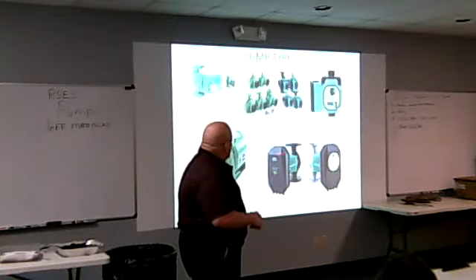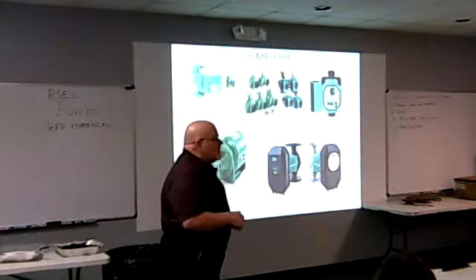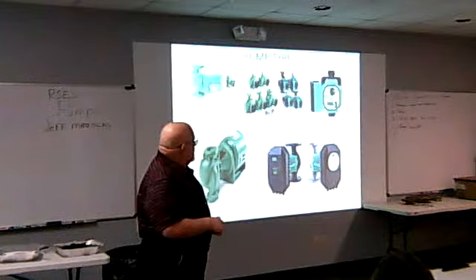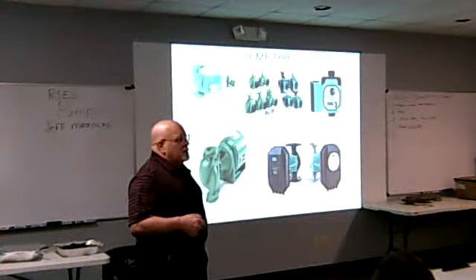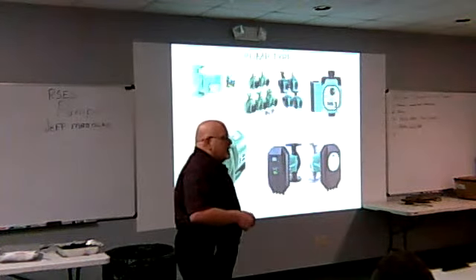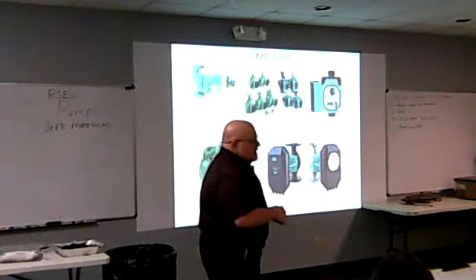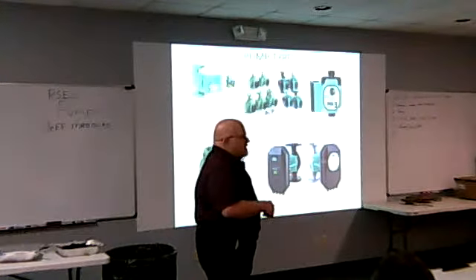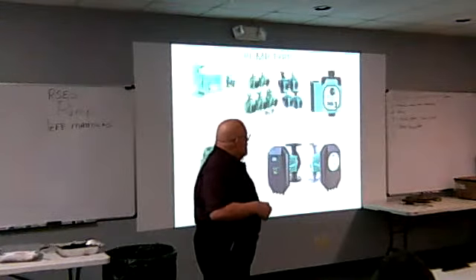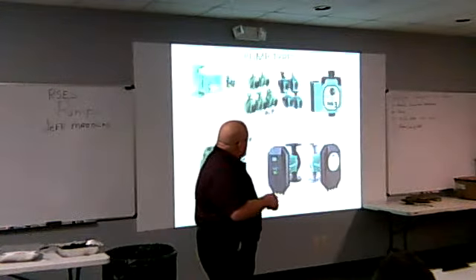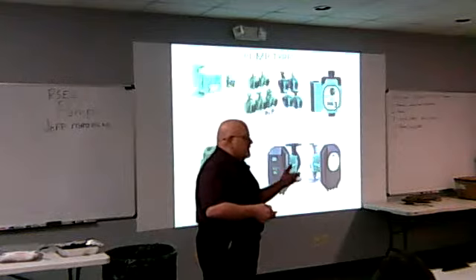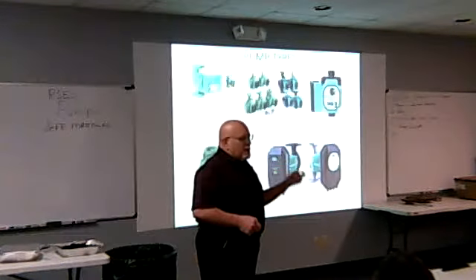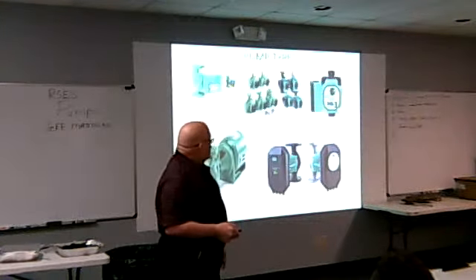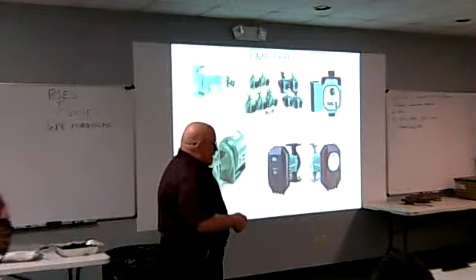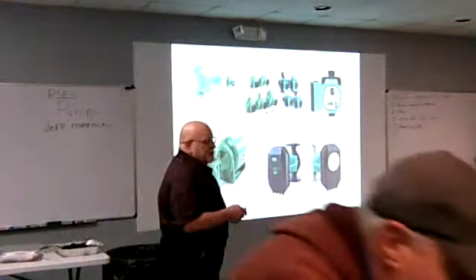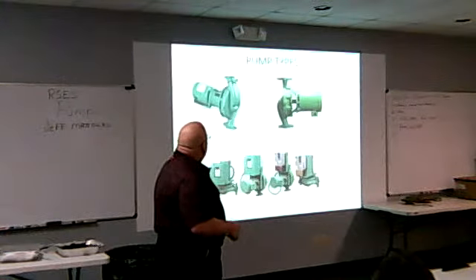This is also the new range. These are all new ECM pumps. Same concept here. They're ECM. You can run them on a 0 to 10 volt signal. You don't need a VFD. They can run self-sensing, 0 to 10, a bunch of different features. We make the 00s like this too, and some of them have their own little dongle that comes with it to set them, and you can do it remotely. So anyhow, this is just the new ranges, the ECM. They're much more energy efficient, which is the reason for them.